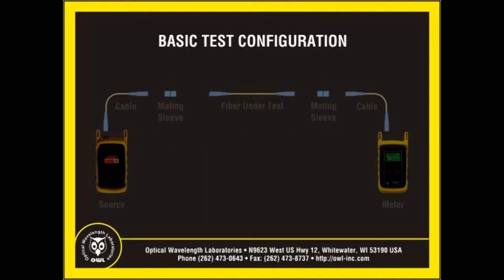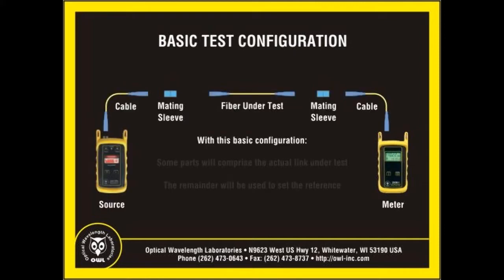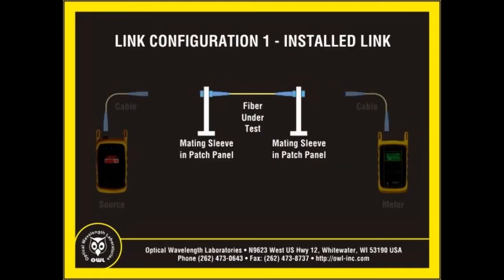While there are multiple reference methods to choose from, the basic test configuration should look like this: source, cable, mating sleeve, fiber under test, another mating sleeve, another cable, and finally the meter. Using this basic configuration, it will be easy to determine what parts belong to the link under test. The remainder will determine your preferred reference method. The first link configuration we will look at is typically considered to be an installed link, where the mating sleeves are probably installed into racks and patch panels. This is by far the most typical link configuration.